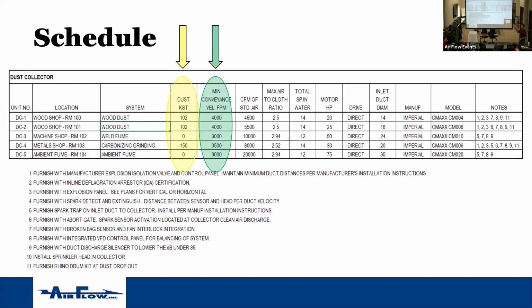So your dust KST. When you design a collector, remember, first thing you do, if I don't know what the KST is, get it tested, right? If it's a new facility, use one of the listed standards, because it'll get you protected. If it's wood dust, I have a KST of 150, it's a standard wood shop. If anyone comes back later down the road and tries to connect a grinding system to it, or maybe they're going to do some buffing of aluminum and try to use the same collector, you're off the hook if anything happens, because you've designed it to a KST set value on your schedule.